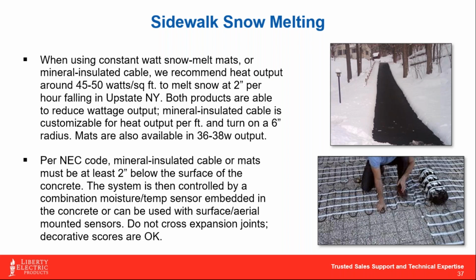So big thing with these immersion systems, generally these are going to be constant wattage cables. As you can see in the picture in the bottom right there, they're using a snow melt cable mat type of product. And those come pre-serpentined, which is great. You don't have to worry as much about that cable spacing or cables touching against themselves. You just want to make sure that each of those runs is separated by about 4 to 6 inches, so that you're getting nice even heat distribution across the footprint.